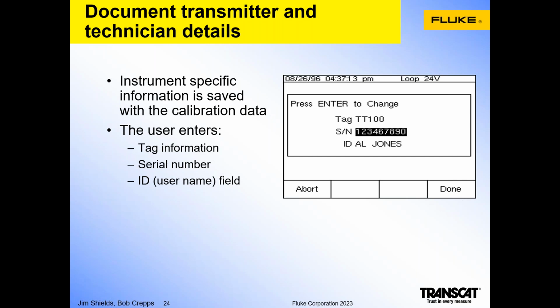When the as found calibration is complete, the tag entry screen is displayed where the tag number of the instrument and the serial number of the instrument are recorded, and the ID of the technician is recorded along with this information, along with the date and the time and the serial number of the calibrator. All are stored in the electronic record for later upload to the calibration management software.